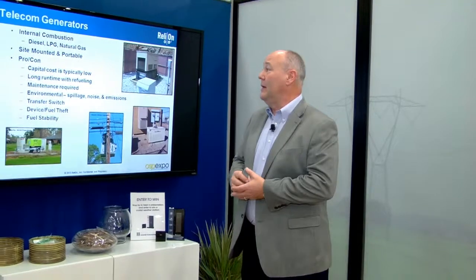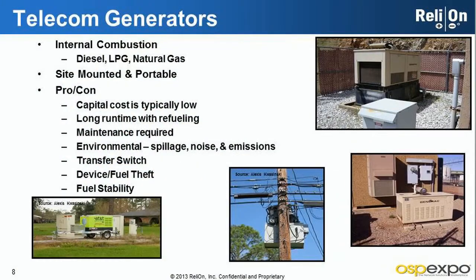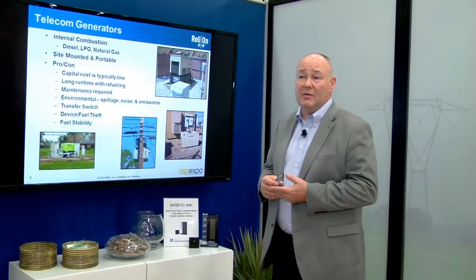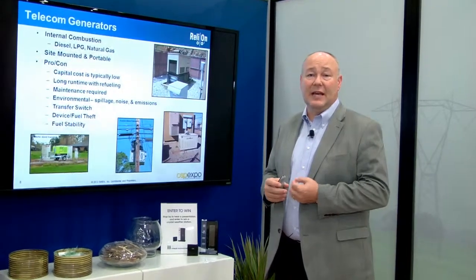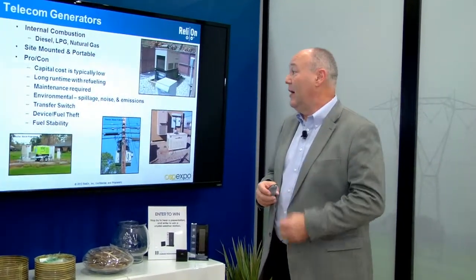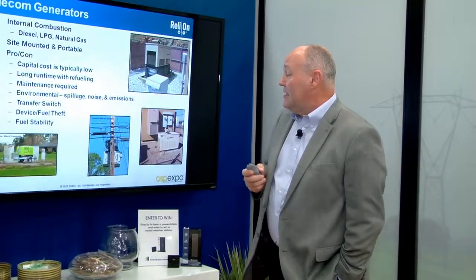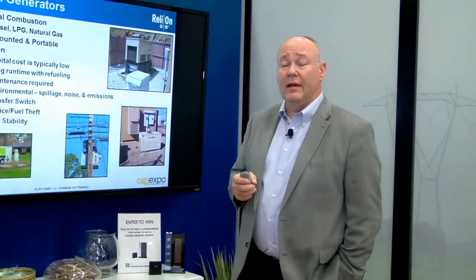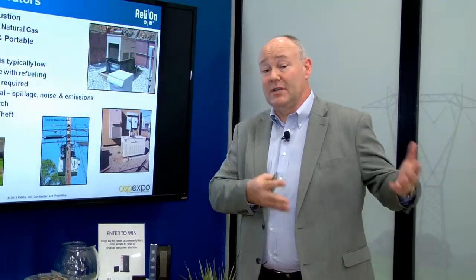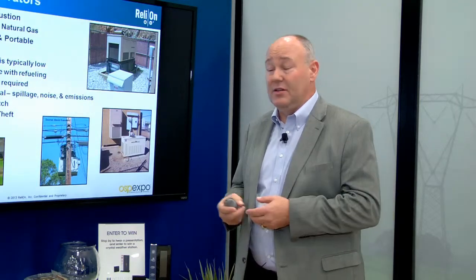On the genset side, the most common fuel is diesel, probably second is propane, and there are some natural gas gensets used where piped natural gas exists. They can be portable - a lot of people use trailer-mounted gensets, making it easy to bring additional power to a site that needs it. Capital cost is typically low or lower than other options, and they offer long run time, lasting as long as you have fuel - just like a fuel cell.